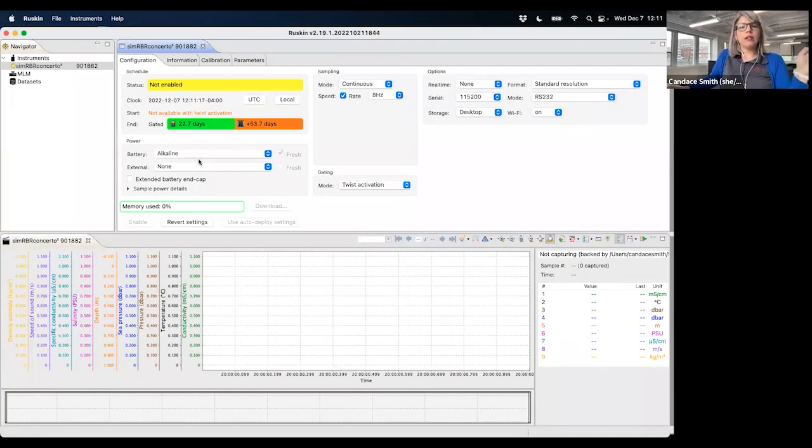So yeah, this actually tells you which chemistries you can use for the instrument that you simulate. This is, again, before you even have an instrument and nothing's connected right now. This will really help you in your planning of how long a deployment will last with a particular instrument.